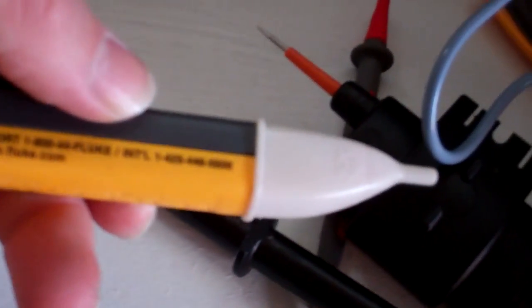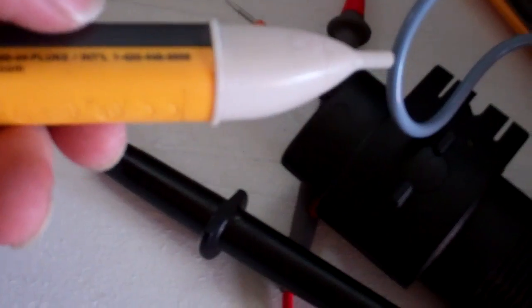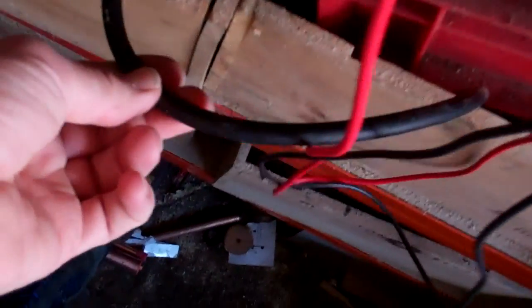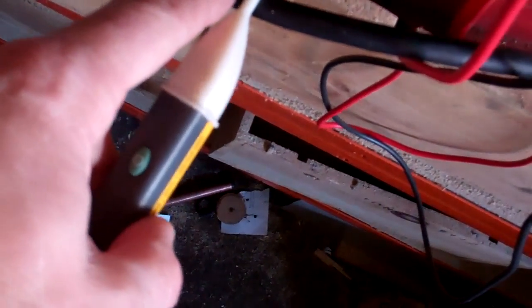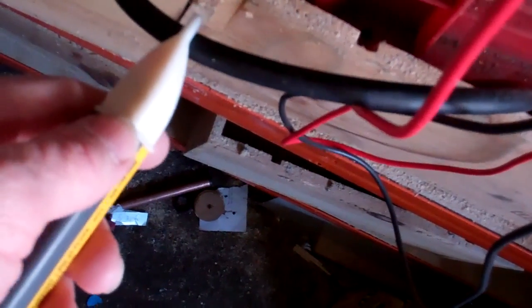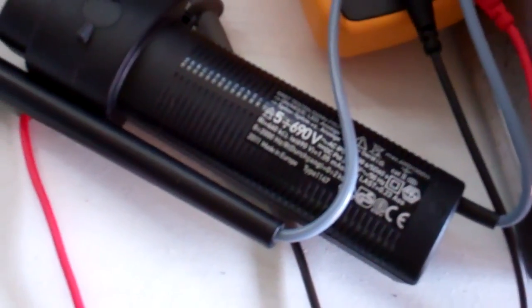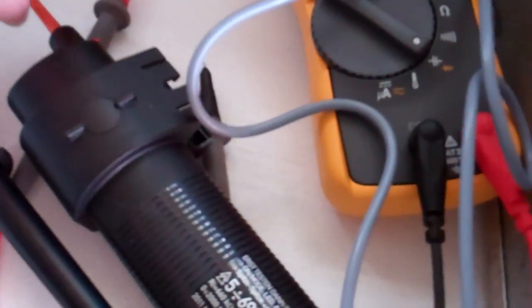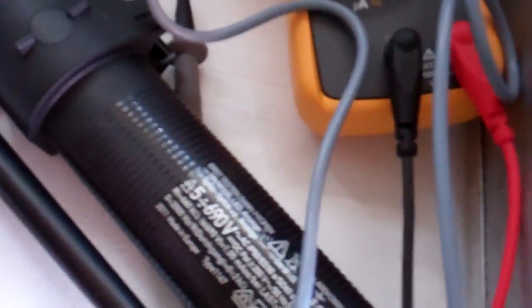But I wouldn't rely on one of these to test whether something was live before I worked on it. 99% of the time it might work fine, but there's going to be that 1% of the time when you're just slightly out of range, or especially on a flex, if you've got a multi-core cable like this that's got 3 strands in it, and you're testing where the earth wire is and the live's around the back, you might think it's dead, and that might be the last thing you know. So I'd always test the terminals with a proper tester before working on anything. And really, you want to test it on a known live first, test what you're testing, and then test it on a known live again, because you need to make sure your meter's working.